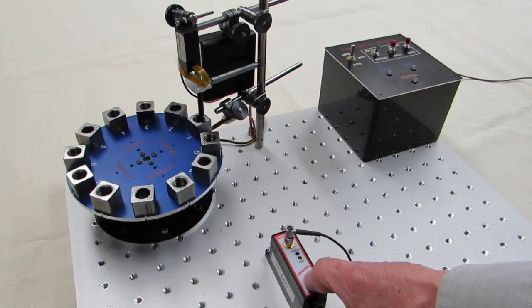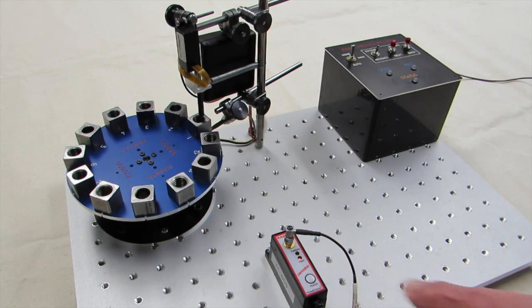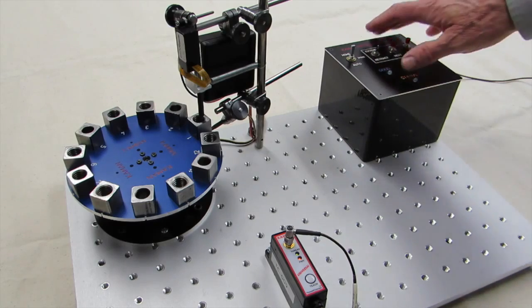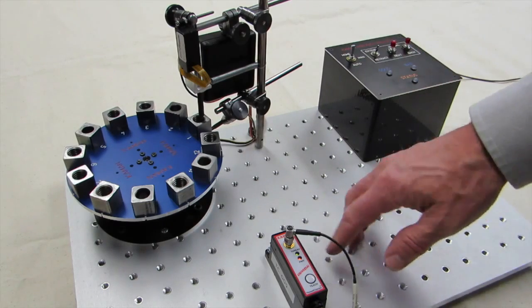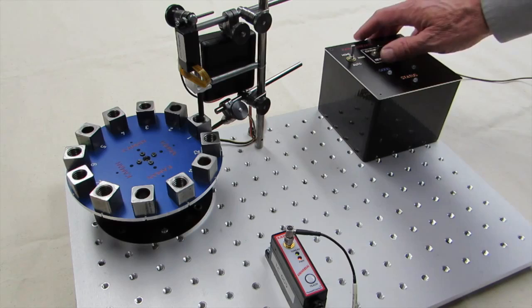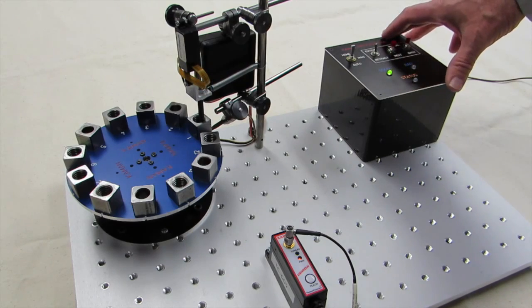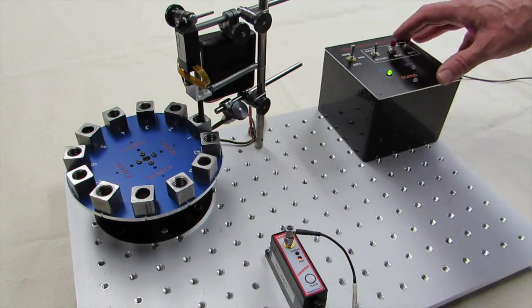You connect the sensor to the SMA connector on the front of the electronics. At that point, you simply push the teach button on the front of the thread checker. That puts it into calibrate mode, and you can see that by the flashing thread light on the electronics. You then insert the probe into a sample of a good threaded part.